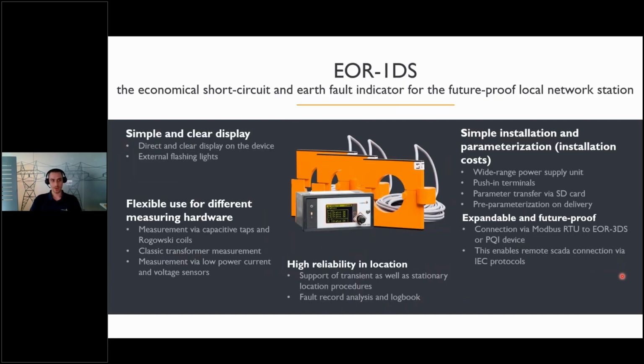So we are now nearly done with the webinar, and that's why I want to give you a short last overview of the EOR-1DS. It is basically an economical short circuit and earth fault indicator for a future-proof local network station. It has a direct and clear display on the device and also offers external flashing lights. It is flexible in use for different measurement hardware. So you can have measurement via capacitive taps and Rogowski coils, or also the classic measurement. But you do also have the option of measurement with highly precise low power current and voltage sensors.